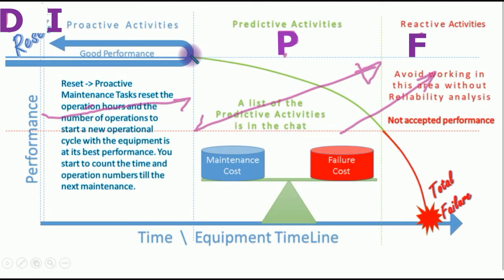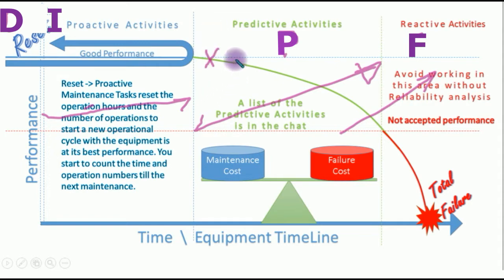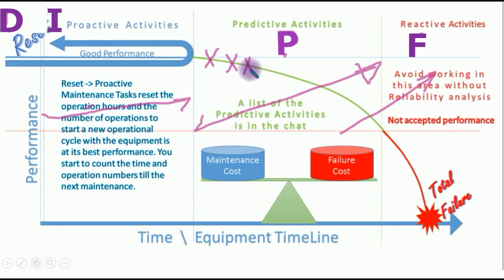Here, the first part is for the oil — so when you make oil or lubricant analysis, you are here. After that, if you are adopting the ultrasonic measurements, you are working here, so the ultrasonic detects a failure at this point. After the ultrasonic, you have the vibration analysis, which detects a failure further along — because at this stage, it's only some changes in the oil, grease, or lubricant.